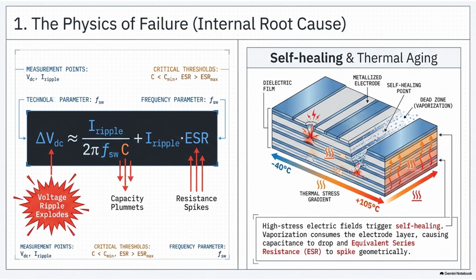It creates carbonized byproducts and degrades the internal structure, which means the equivalent series resistance, or ESR, begins to spike. Wait, so it's the double whammy. The component is simultaneously losing its ability to buffer energy while becoming more resistant to the flow of current. And the mathematics of this decay are just punishing, because the voltage ripple amplitude across that capacitor is inversely proportional to its capacitance, and directly proportional to its resistance. So if your capacitance is decaying while your resistance is climbing, the voltage ripples don't just increase linearly. They explode. Right, they grow exponentially. The system is pushed into a runaway thermal and electrical spiral.